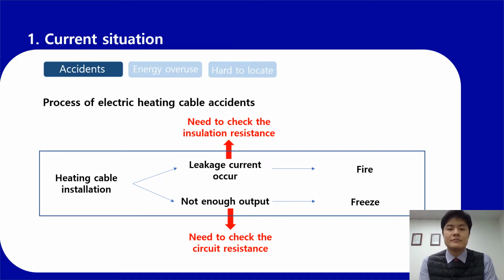Heat tracing systems use heating cables in power plants for freeze protection and maintaining the temperature. Fire and freeze are two representative accidents caused by heating cables. Bad insulation of the heating cable causes leakage current, and it can cause a fire on the site. To detect the danger of fire and prevent the accident, the heating cable's insulation resistance must be checked regularly.